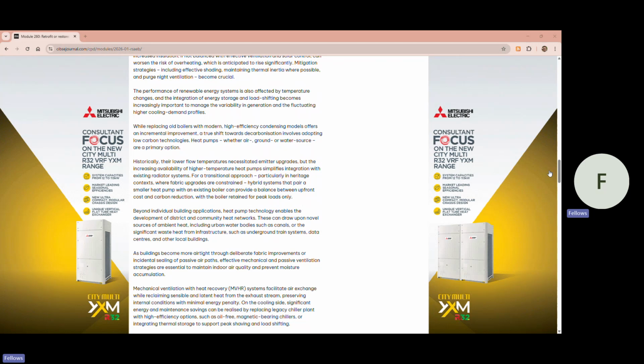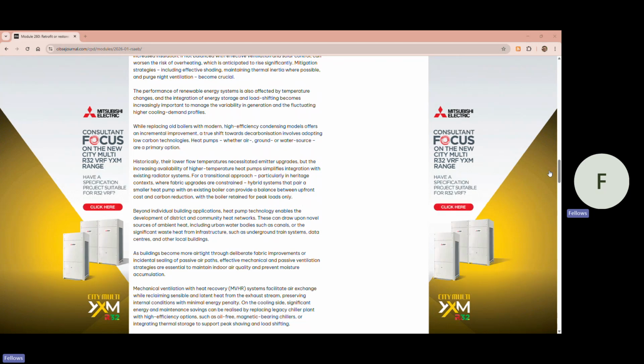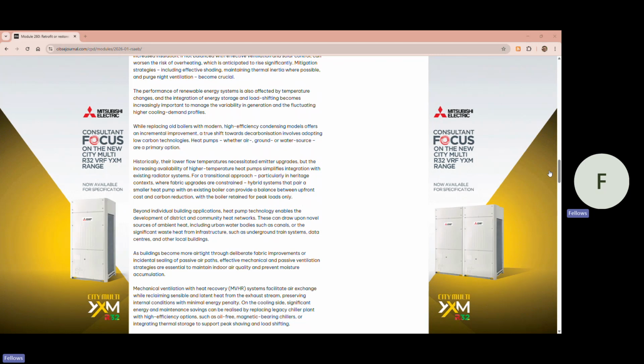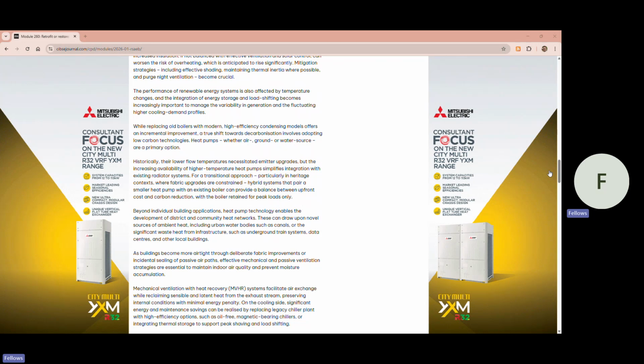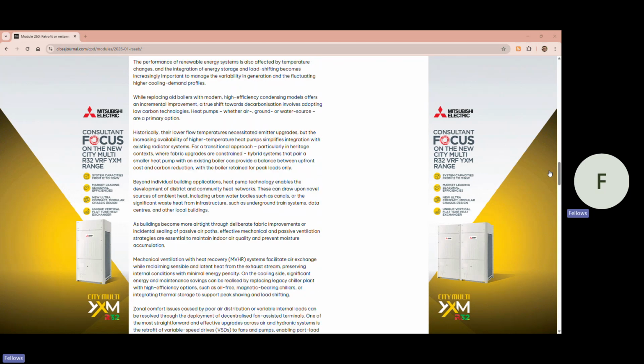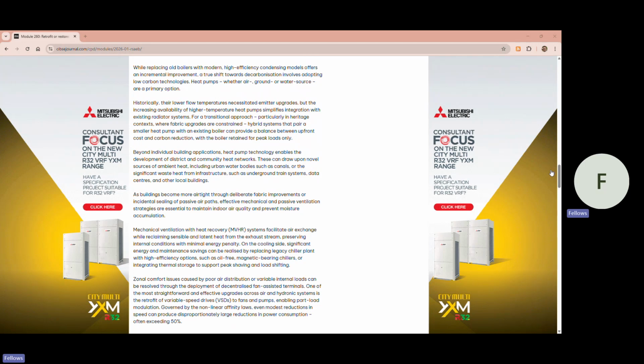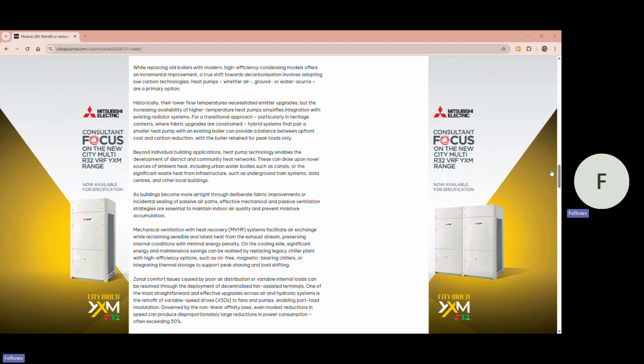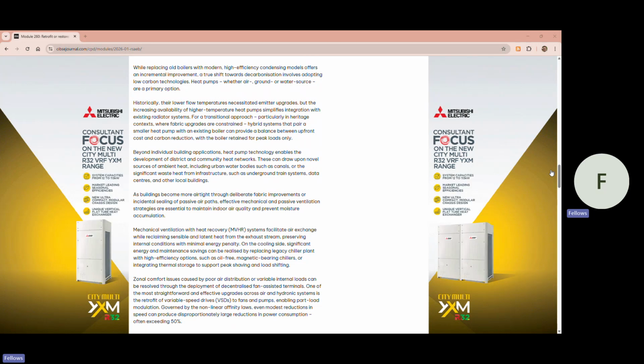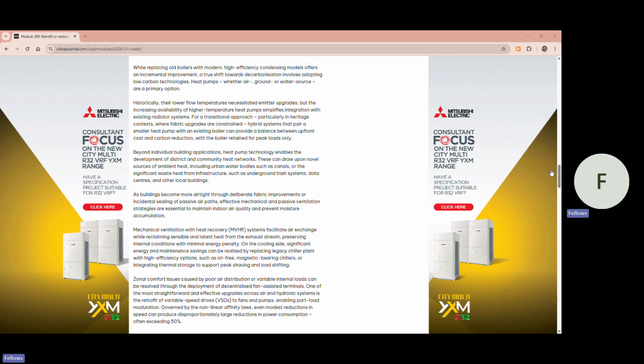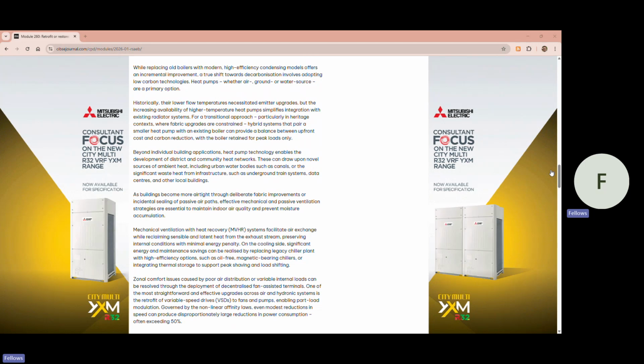with existing radiator systems. For a transitional approach, particularly in heritage contexts where fabric upgrades are constrained, hybrid systems that pair up a smaller heat pump with an existing boiler can provide a balance between upfront cost and carbon reduction, with the boiler retained for peak loads only. Beyond individual building applications, heat pump technologies enable the development of district and community heat networks. These can draw upon novel sources of ambient heat, including urban water bodies such as canals, or the significant waste heat from infrastructure, such as underground train systems, data centers, and other local buildings.